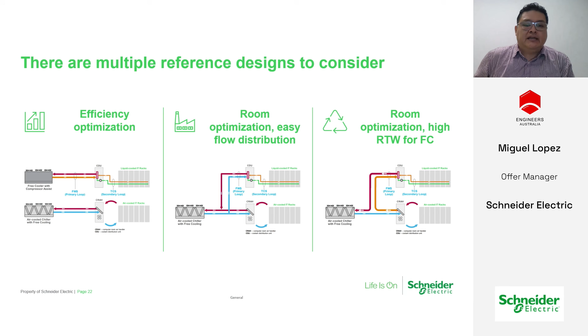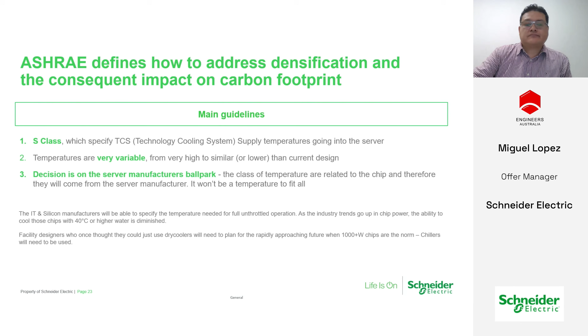Moving along. So going back to the source of truth. The source of truth with liquid cooling is obviously ASHRAE. ASHRAE is obviously trying, very quickly, to define and address these design challenges with liquid cooling. So I would urge you to refer to ASHRAE for detail on the following slides. But what I'd like to do now is just show you some of the impact of the work that ASHRAE is doing, such as S classification of the fluids on the TCS loop, or the Technology Cooling System loop, and some of the knock-on effects that will have.